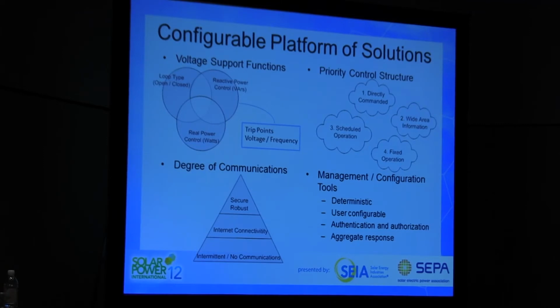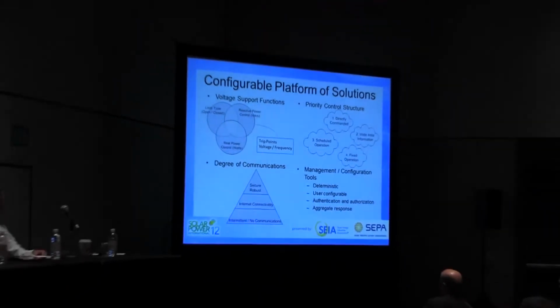Lastly would be fixed operation. There are sites where you don't need reactive power—it's okay to just continue being a watt source, and you don't need communications. We have sites with needs for each of these individual priority control structures, and for some, if communications go away, it falls to the next level down. That's what I'm postulating as a path forward until we get closed loop voltage control.